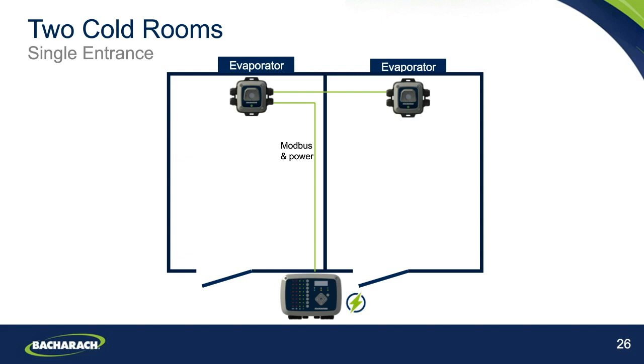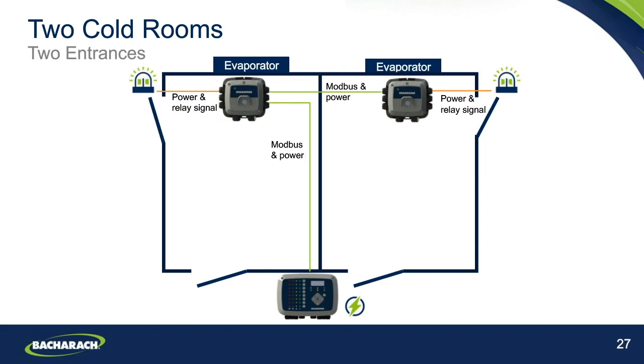there is a potential danger. If we throw on another entrance to each of these cold rooms, we can see that the setup stays broadly the same, but again, we need to be looking at adding the additional horn strobes into the system here, so that we're providing those audible and visual alarms outside of each entrance into the refrigerated space, which of course again falls in line with those ASHRAE 15 code requirements.